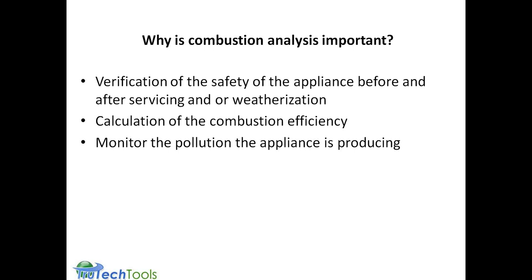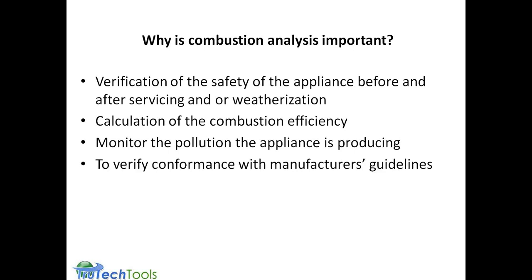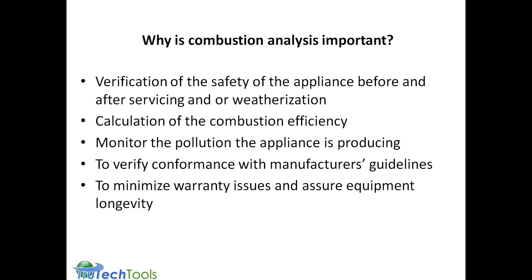We can also monitor the output with a combustion analyzer, the output of pollution or toxic gases. And we want to verify the conformance with the way the manufacturer recommends the product be set up and operated, taking a look at the temperature output of the flue gas, taking a look at the pressures of the fuel coming in. In providing all these kinds of checks on the equipment, we can help minimize warranty issues if you're a service technician, and you can also assure the equipment's operating safely and with the longest service life possible.